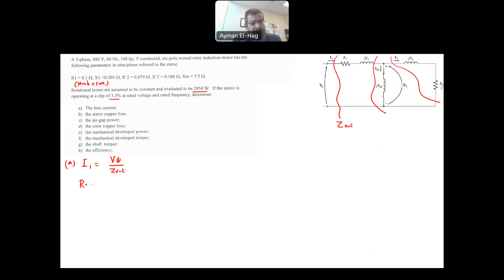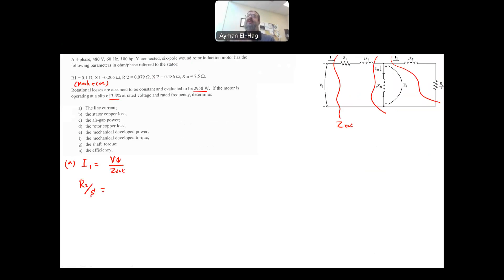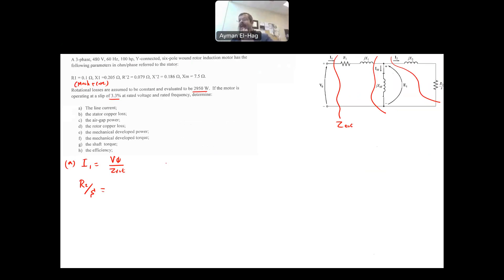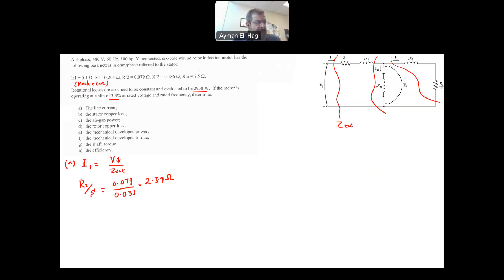R2 over S — the reason we divide R2 by S is because the frequency of the rotor is different than the frequency of the stator; the induced voltage in the rotor is different. Because of that difference in frequency, to do the matching of frequencies, we have to divide R2 by S. So this is equal to 0.079 divided by S, which is 0.033, giving 2.39 ohms.